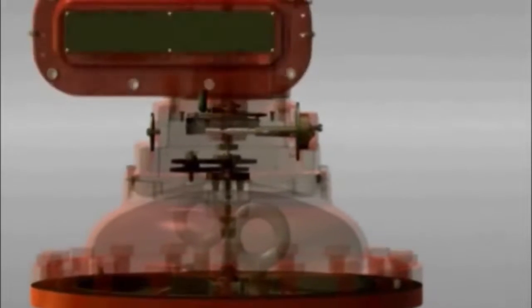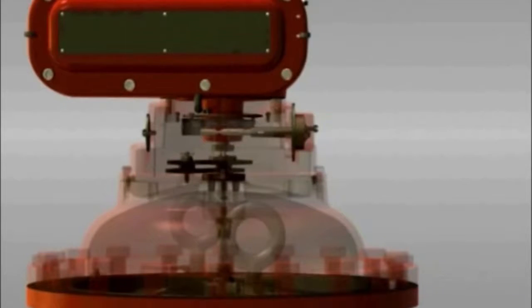The rotor assembly is connected to the meter output shaft by a gear coupling. Each revolution of the output shaft, therefore, represents a precise volume that has passed through the meter. The external gear train changes the meter volume into the preferred measurement unit, such as gallons, barrels, or liters.